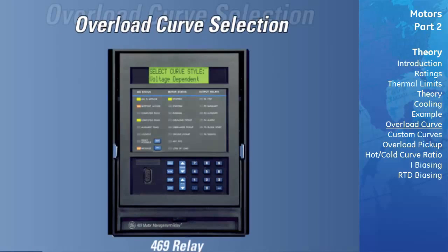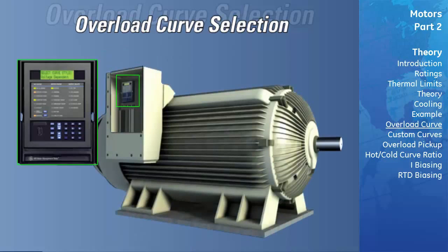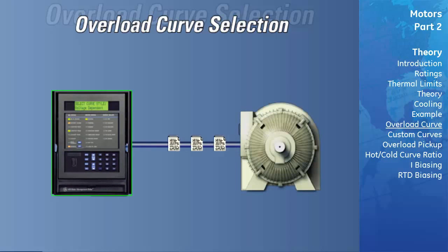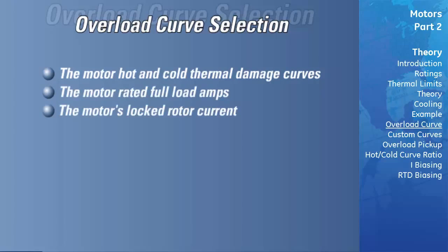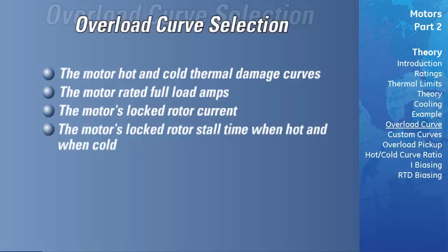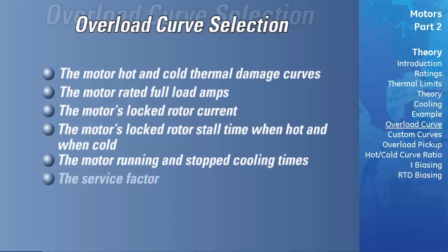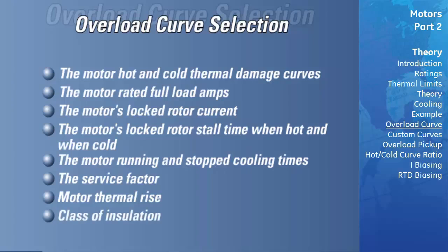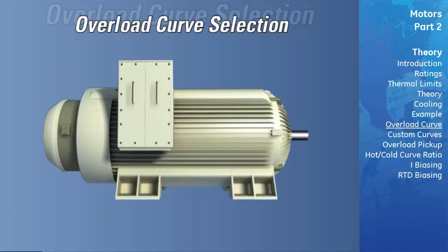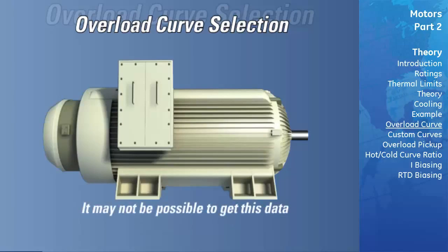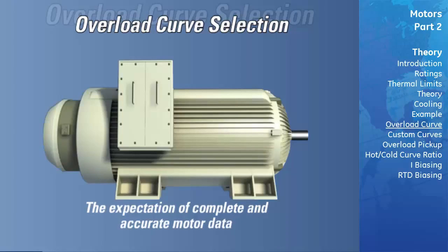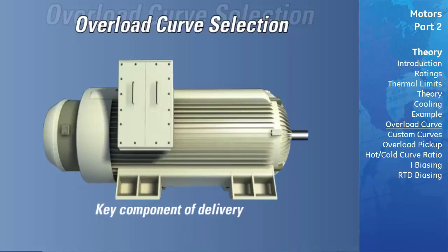Now that you understand the concept of motor thermal modeling, we will go into the relay settings. The first step is to obtain accurate motor data from the motor supplier. This data must include critical motor information. Note that on many large custom motors, this data may not be supplied as part of the delivery package unless requested by the customer. Once the motor has been shipped, it may not be possible to get this data. It is therefore critical that the customer makes it clear to the motor supplier the expectation of complete and accurate motor data being shipped with the motor.